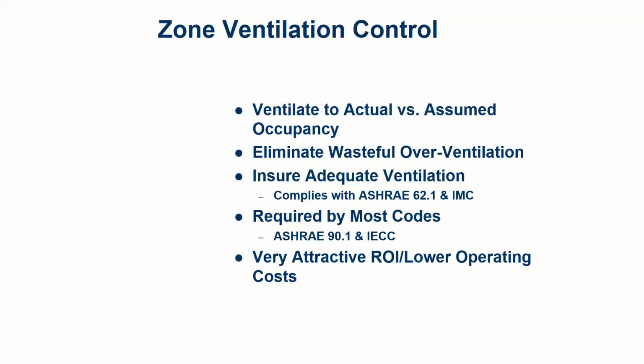If you want to ventilate more, all you have to do is change your set point. Instead of leaving it at 1100 parts per million, just put it down to like 500 parts per million, something like that, and you'll get the normal amount of ventilation - a higher ventilation rate.